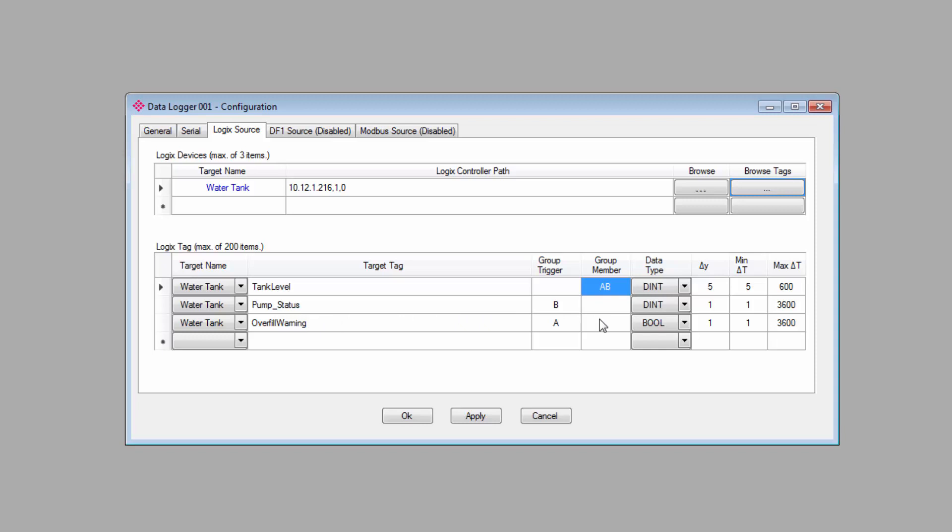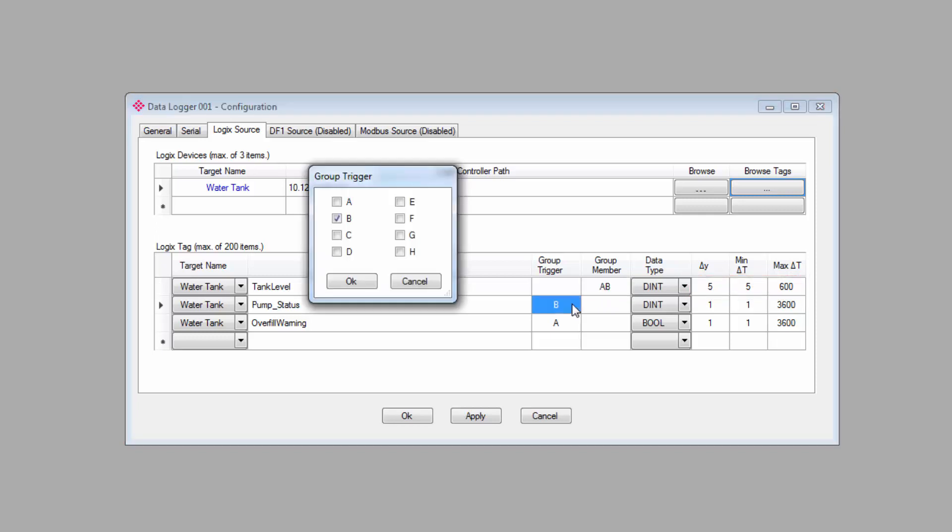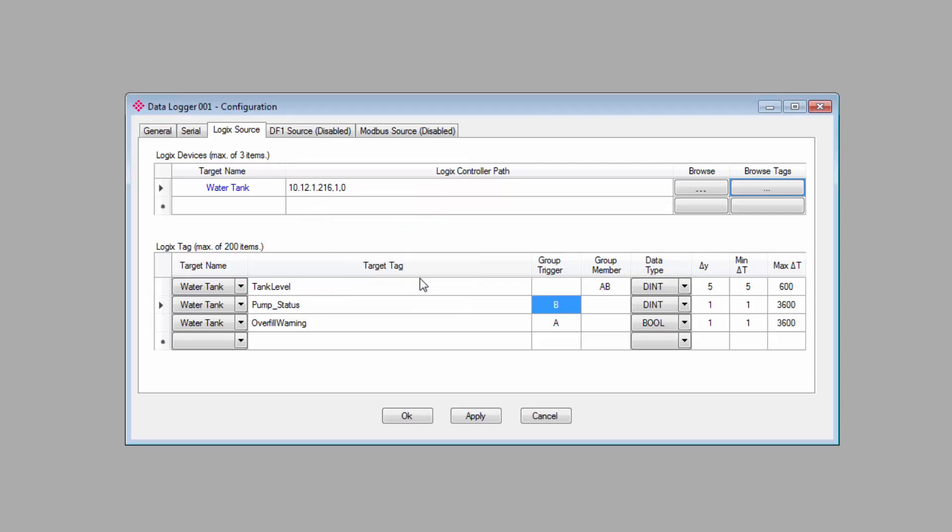The tank level is a member of both of these groups, so either event will trigger a log for that tag, but it's only a member. It's not a trigger itself, so whenever the tank level logs in accordance with the parameters here, it won't trigger a log for the pump or the warning. The software supports up to eight different groups, so you can get pretty fancy linking different variables and events together should you choose.